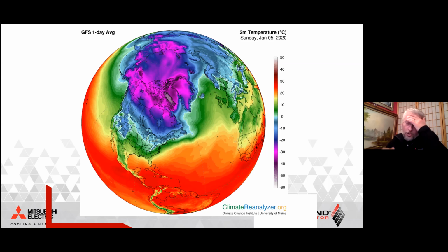And a good designer will look at not only what the maximum capacity of the system is at really cold temperatures to make sure people are warm enough to meet their needs, but it's also critically important that the sizing is not so great that the system can't turn down low enough to satisfy the needs of the home during the shoulder seasons. And some amount of cycling, turning on and off, will occur on every system. It's just inherent. When you get to a certain point, you need just a teeny bit of cooling, and the system's going to turn on a little bit. But what we want to avoid in the course of sizing is having so much equipment or so large equipment that it's cycling for significant portions of the year. And so that's one of the considerations that has to be taken into account with high performance homes. And one of the key strategies for avoiding that kind of a problem is to have multiple outdoor units.